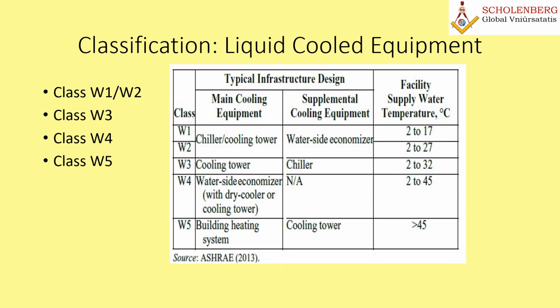Well, when we say liquid cooled equipment, they are again classified as W1, W2, W3, W4, W5. Now let's check and see one by one. For any piece of datacom equipment to comply with a particular environment class, it must be able to reliably provide its full operational capabilities over the entire classification temperature range based on non-failure conditions. What are class W1 and class W2? These are typically data centers that are traditionally cooled using chillers and cooling towers, but with an optional water side economizer to improve the energy efficiency depending on the facility's operation and location.